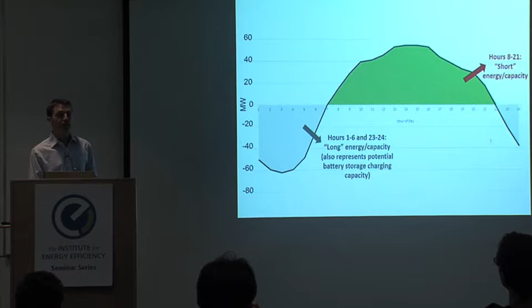In terms of load in this 66 kV Goleta-Santa Barbara load pocket, our peak load is about 285 megawatts, and we're about 15 of that. Between the three 66,000 volt lines, they've got about 230 megawatts of capacity—that's how much they can deliver. So in the worst case scenario, they'd be short in the day by about 55 megawatts, which is where that number came from. This zero line represents the full capacity of the secondary system. At night they've got surplus capacity; in the day they're about 55 short. This is straight out of an Edison presentation with their solicitation package, so we'll be paying close attention to try and chase some of that funding for on-site storage.